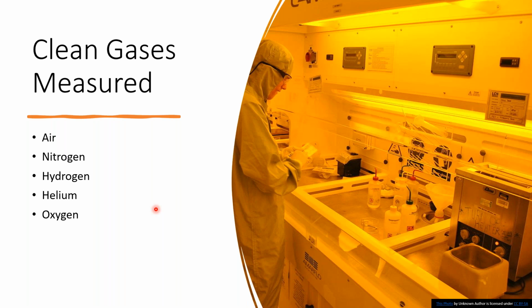And then the other nice thing that I like to point out is that, when you're working with a company, you want to make sure that you're working with a company that will actually calibrate on that specific fluid. So when you're working with hydrogen, for example, hydrogen does not have a correction factor that is consistent. So what does that mean? It means that if you're working with someone, you want to make sure that they're calibrating on hydrogen, because if they're going to calibrate on air and try to convert it to hydrogen, you're not going to get an accurate unit, because there is no consistent factor that can be applied from 0 all the way up to maybe 100% of that flow range. The factor is going to change. So that's why it's best to work with a company that's used to doing the calibrations on the fluids that you are working with.